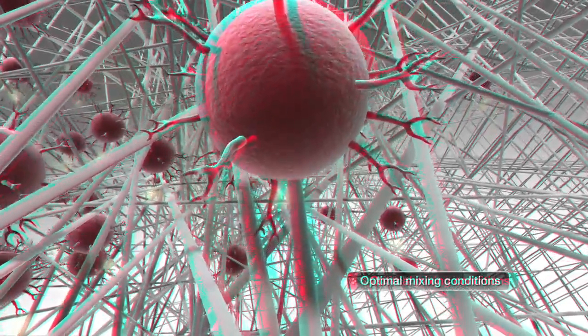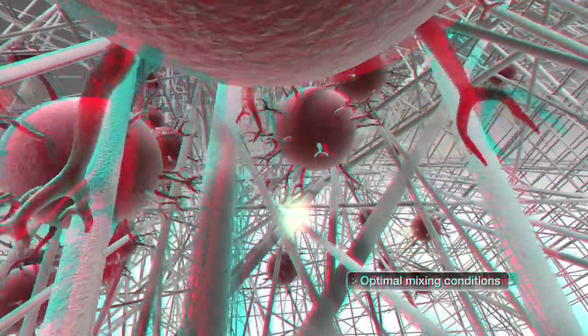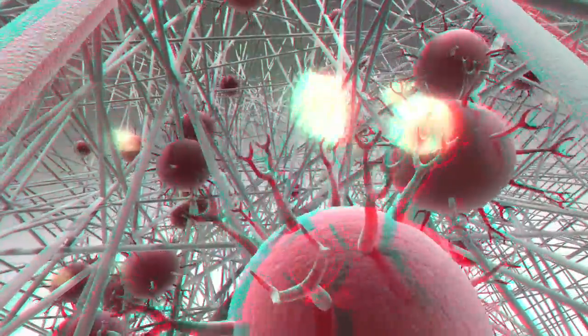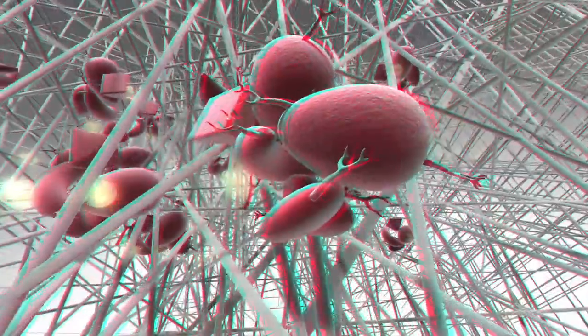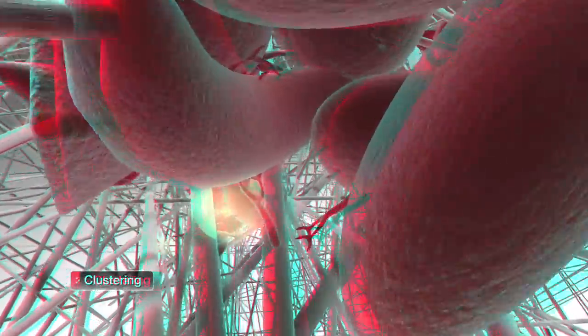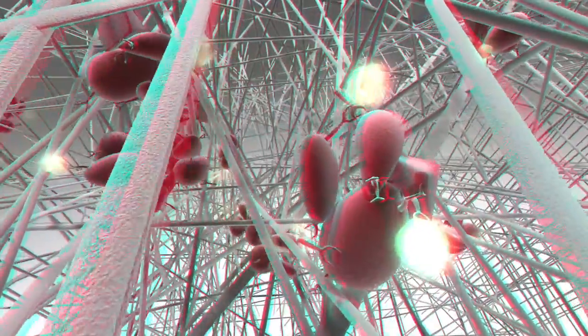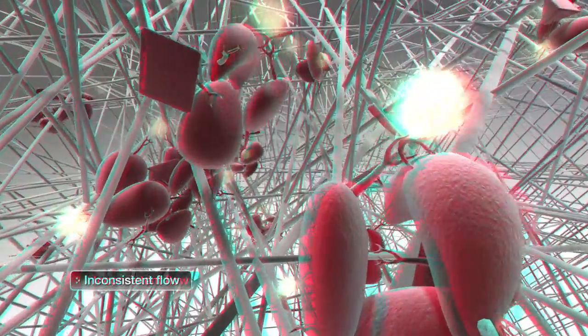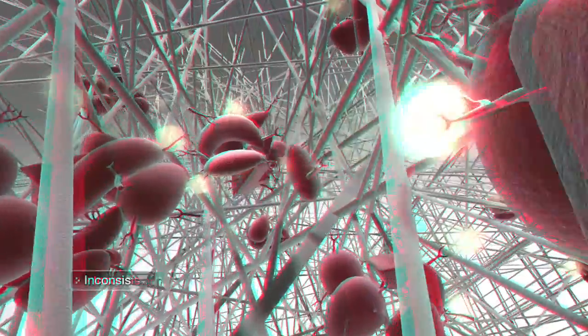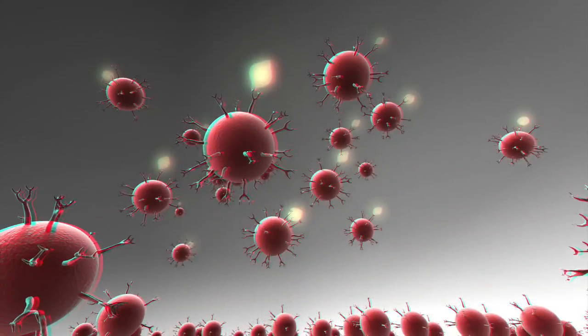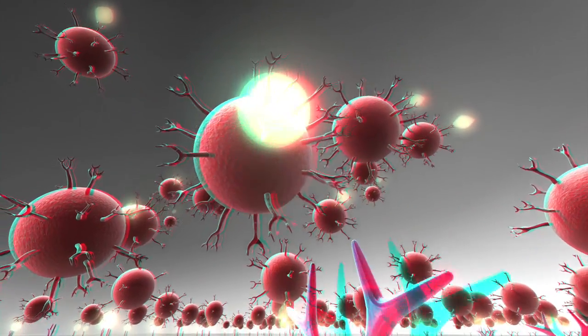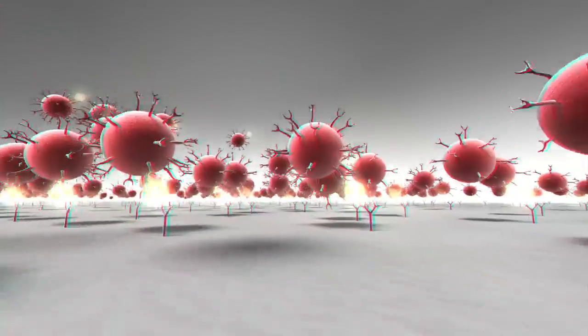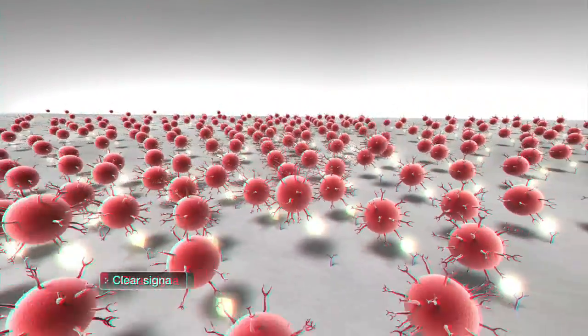The antigens within the blood attach evenly to the antibodies preloaded on the gold conjugate, ensuring optimum mixing conditions of the sample and the gold as it journeys through the membrane. Poor quality gold can cluster and become trapped in the membrane. As the antigen reaches the test line, it forms a strong bond with the immobilized antibody to form a clear, accurate, consistent signal.